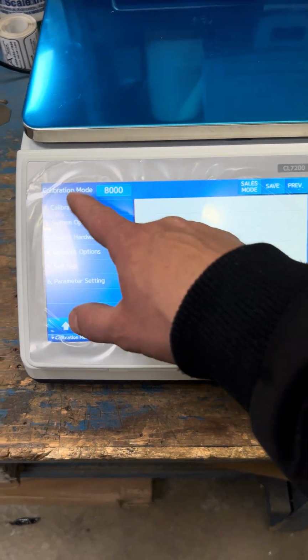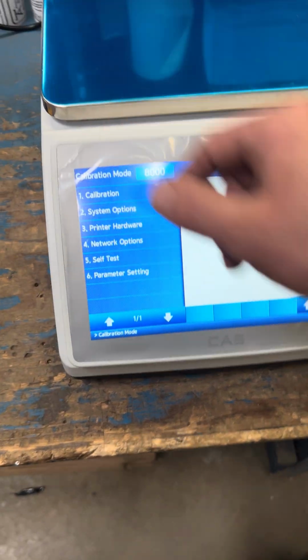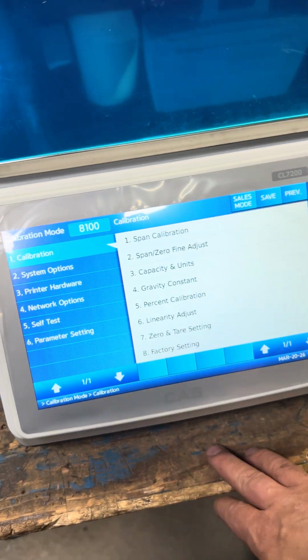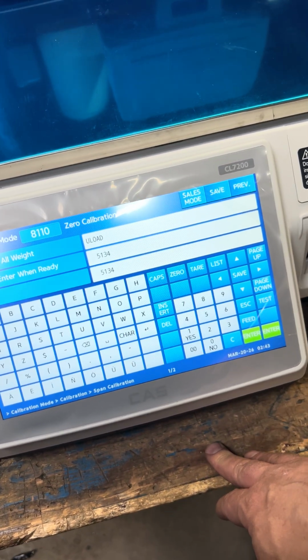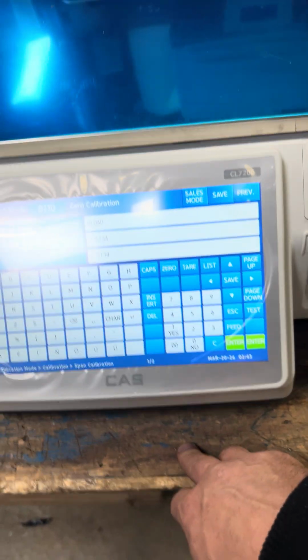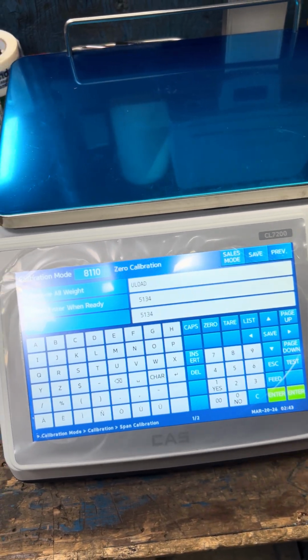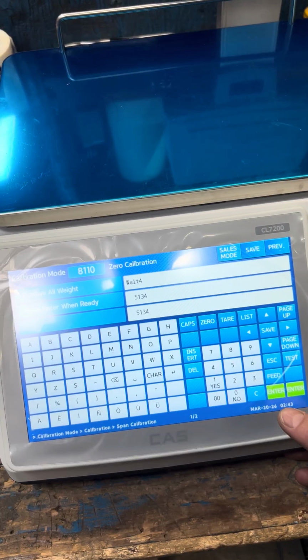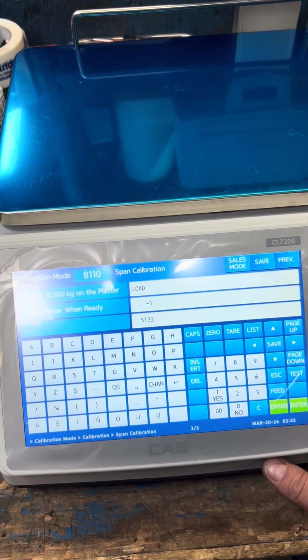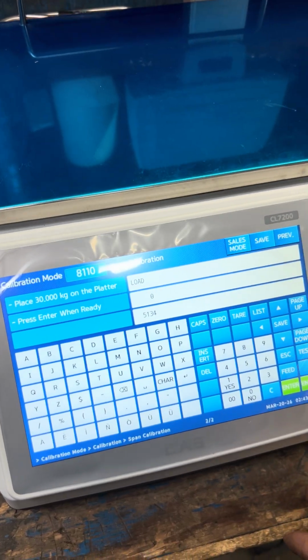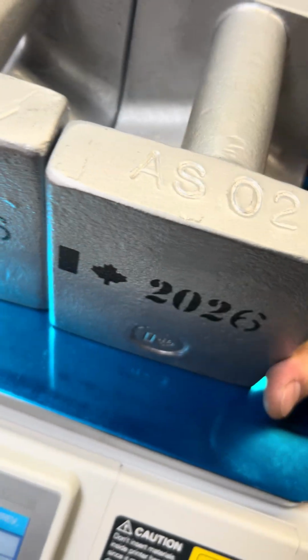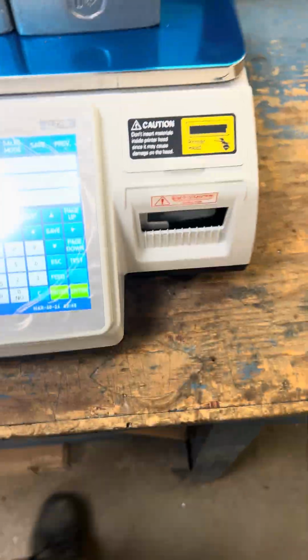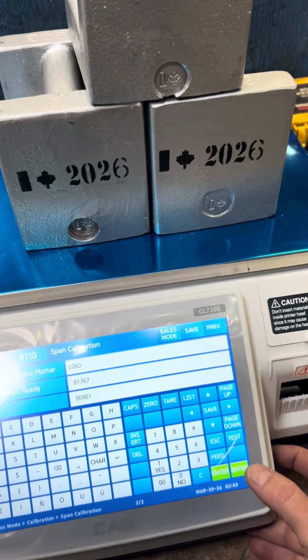And now it brings us directly to the calibration mode because we turned on the switch. So we go calibration, span calibration. Remove all the weight, we press enter. It's calibrating now. Now it's asking us about the weight. 30 kgs. So we put 30 kgs on the platter. We have 30 kgs and press enter.